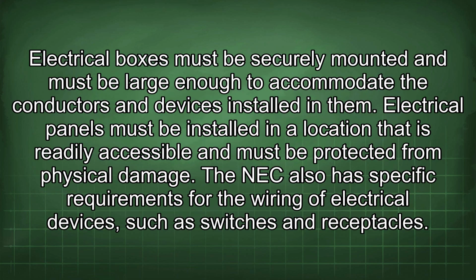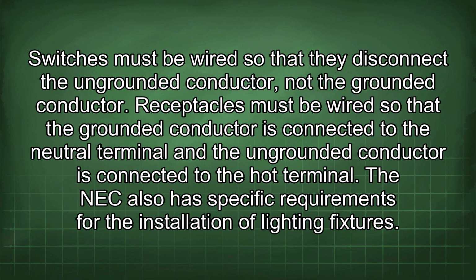The electrical boxes must be securely mounted and must be large enough to accommodate the conductors and devices installed in them. The electrical panels must be installed in a location that is readily accessible and must be protected from physical damage. The NEC also has specific requirements for the wiring of electrical devices, such as switches and receptacles. Switches must be wired so that they disconnect the ungrounded conductor, not the grounded conductor. Receptacles must be wired so that the grounded conductor is connected to the neutral terminal and the ungrounded conductor is connected to the hot terminal.